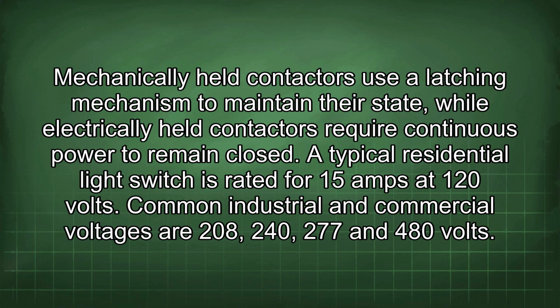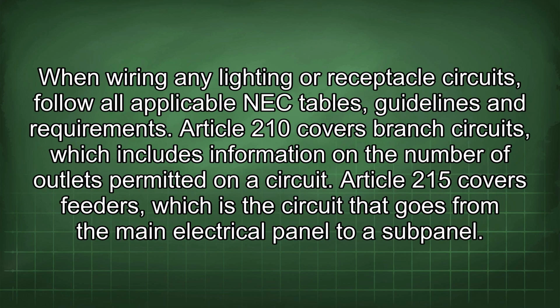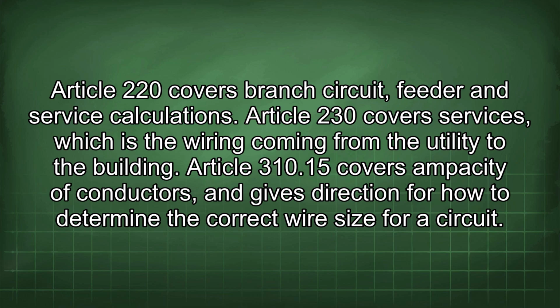Common industrial and commercial voltages are 208, 240, 277 and 480 volts. When wiring any lighting or receptacle circuits, follow all applicable NEC tables, guidelines and requirements. Article 210 covers branch circuits, which includes information on the number of outlets permitted on a circuit. Article 215 covers feeders, which is the circuit that goes from the main electrical panel to a subpanel. Article 220 covers branch circuit, feeder and service calculations. Article 230 covers services, which is the wiring coming from the utility to the building.